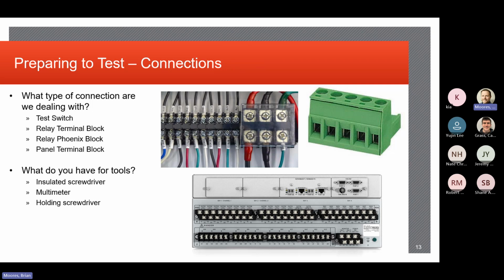But these are some of the different kinds of test block terminals that we might encounter. Simple terminals with screws. We've got these little green, what I call Phoenix connectors, which are sort of a compression type connector. The relay panel there on the lower right hand, that looks like an SEL relay. So again, more of the screw type terminals.